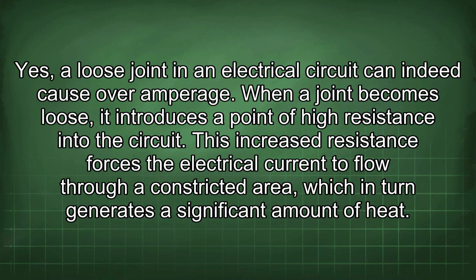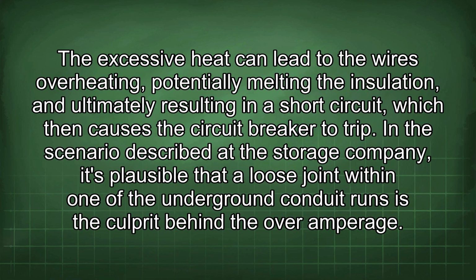Yes, a loose joint in an electrical circuit can indeed cause overamperage. When a joint becomes loose, it introduces a point of high resistance into the circuit. This increased resistance forces the electrical current to flow through a constricted area, which in turn generates a significant amount of heat. The excessive heat can lead to the wires overheating, potentially melting the insulation, and ultimately resulting in a short circuit, which then causes the circuit breaker to trip.